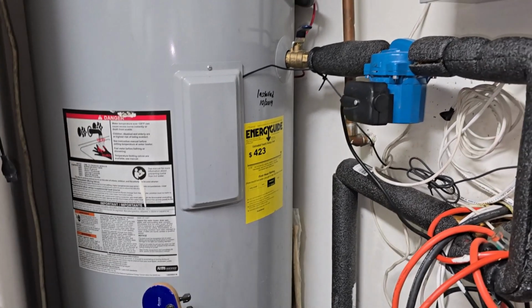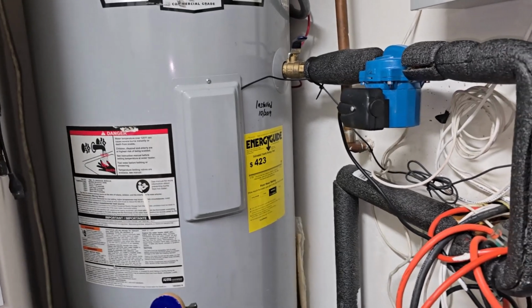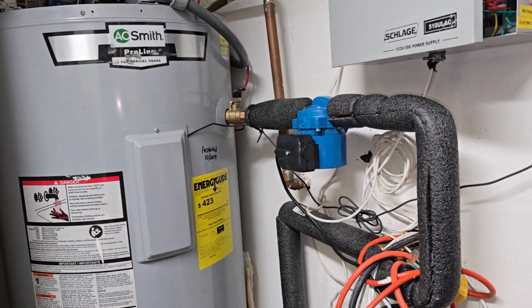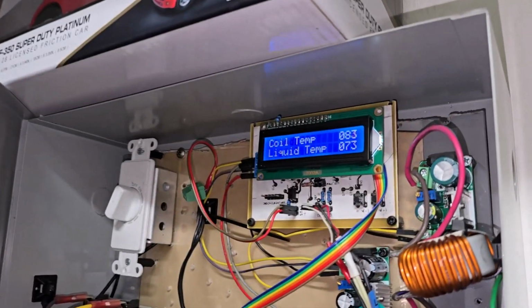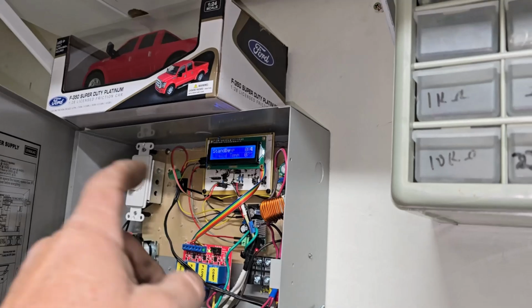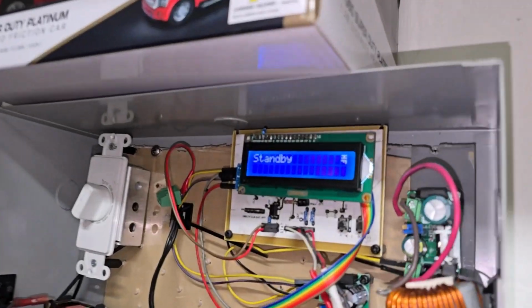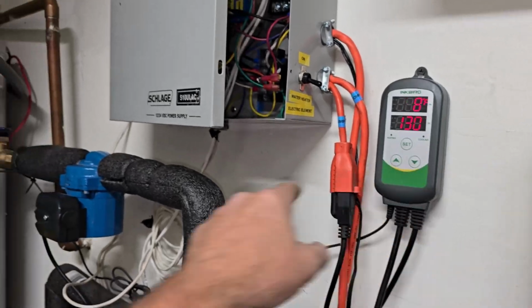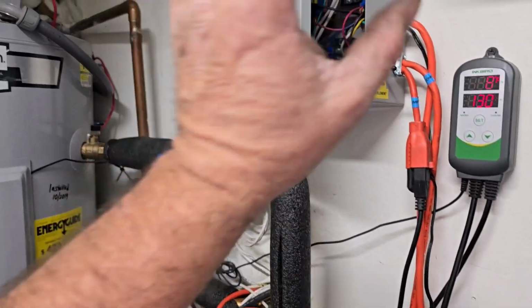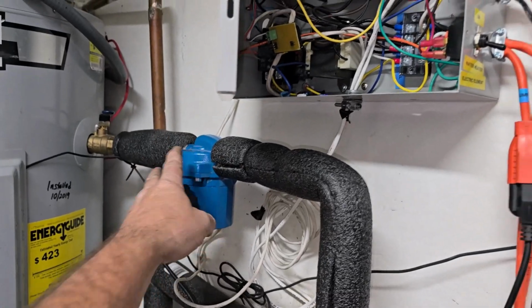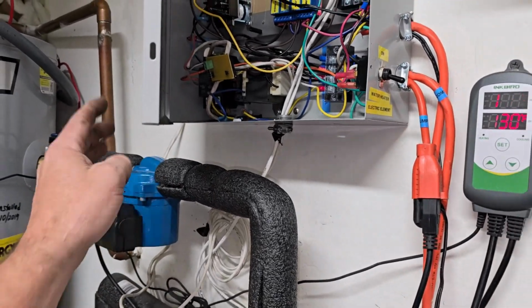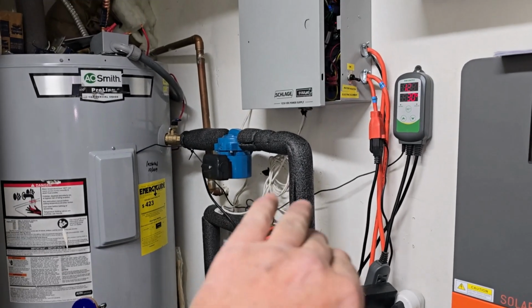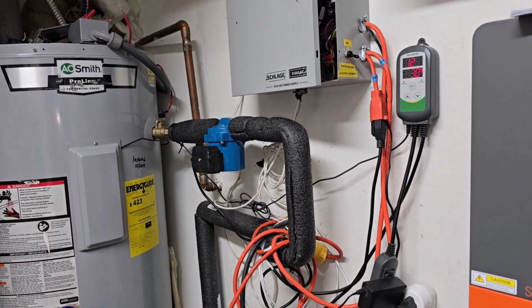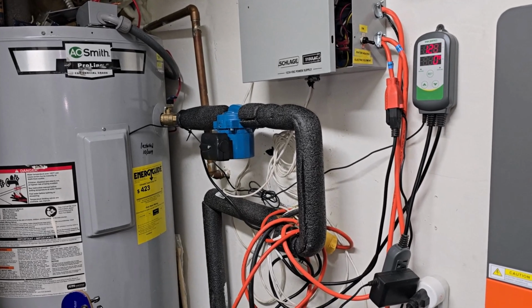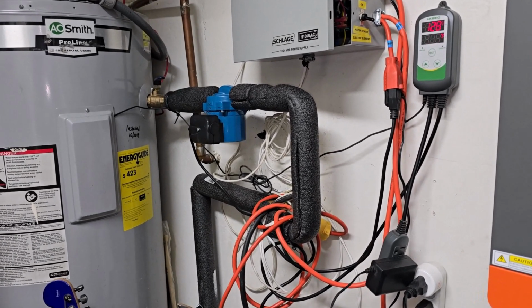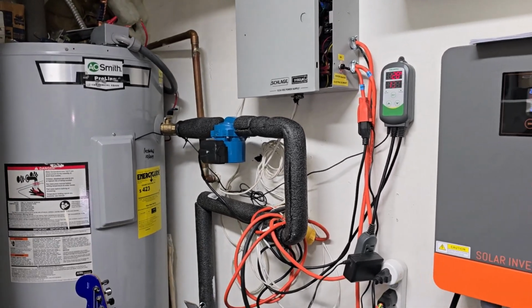Because I used to start out with a water source heat pump mounted in my garage, and then I built my own little one to heat this, and it's evolved from there. So this is my homemade controller - it says it's in standby. I could read my suction temperature and liquid line temperature from right here. This just has a probe down in the middle of the tank there to turn it on. And then this cycles my pump, which I got better at after a while - I realized, to keep the minimum heat rise and always just have hot water coming back, I cycle the pump with the temperature of the liquid line out there, which tracks with the temperature of the water in the coaxial heat exchanger.